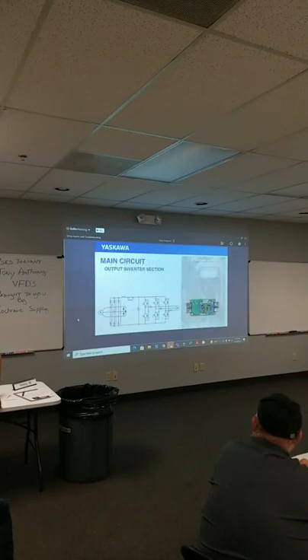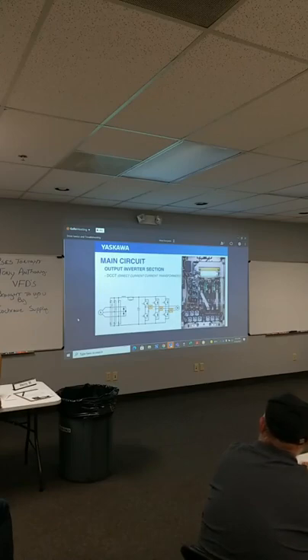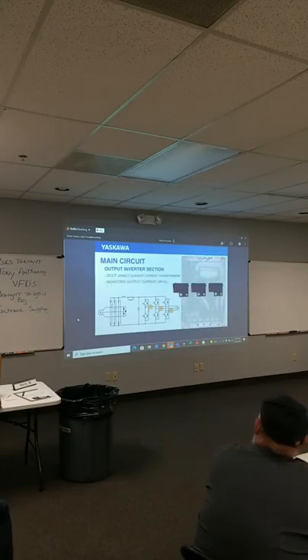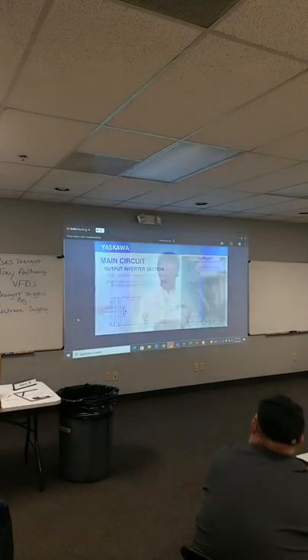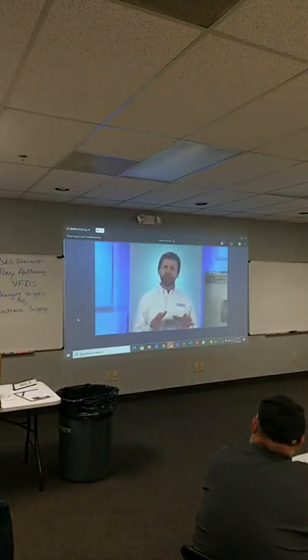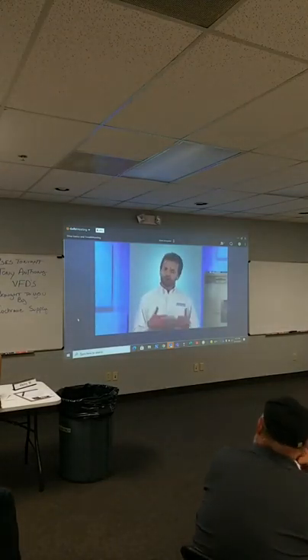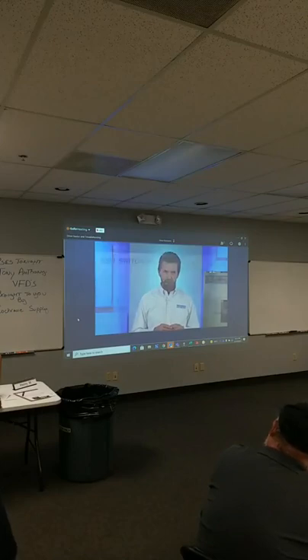After the IGBTs come the DCCTs, or direct current current transformers. The DCCTs monitor output current on all three phases going to the motor. This can be used for control and motor protection. Let's explain how these IGBTs work together to build this three-phase power.